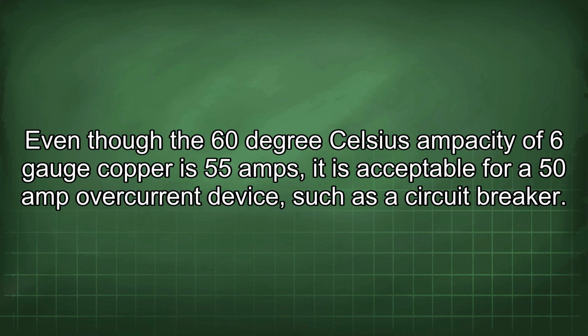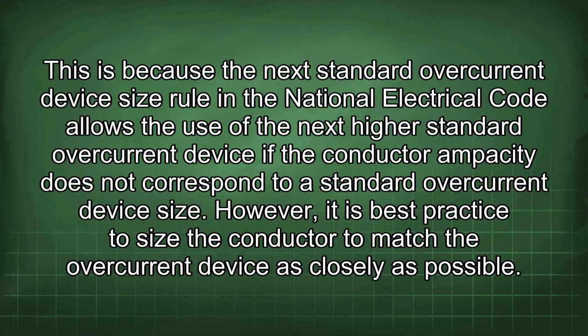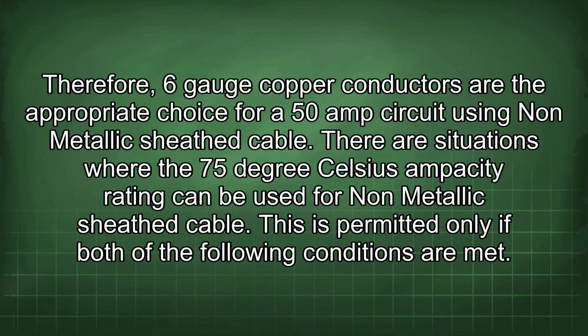Even though the 60°C ampacity of 6-gauge copper is 55 amps, it is acceptable for a 50-amp overcurrent device, such as a circuit breaker. This is because the next standard overcurrent device size rule in the National Electrical Code allows the use of the next higher standard overcurrent device if the conductor ampacity does not correspond to a standard overcurrent device size. However, it is best practice to size the conductor to match the overcurrent device as closely as possible. Therefore, 6-gauge copper conductors are the appropriate choice for a 50-amp circuit using non-metallic sheath cable.